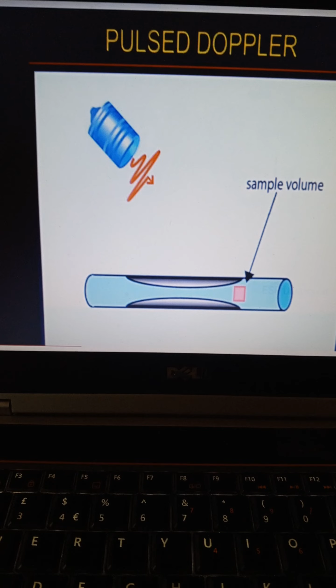Now we come to another modality which is called pulse wave Doppler. Pulse wave Doppler measures velocities at a certain location, at a certain point. That is the advantage. So usually there is a source, which is the transducer, and the receiver, which is the blood vessel with red blood cells. It has one crystal sending the pulse, then it will wait for a return signal.